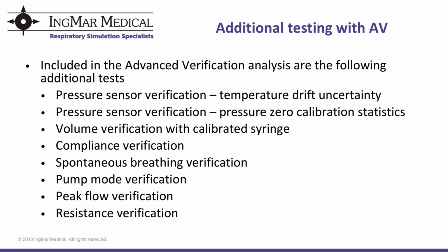On the slide in front of you, you can see all of the different tests we perform in addition to the standard calibration when we perform an advanced verification. The array of additional tests that we run range from pressure sensing and evaluation of resistance, compliance, and volume, to name a few.